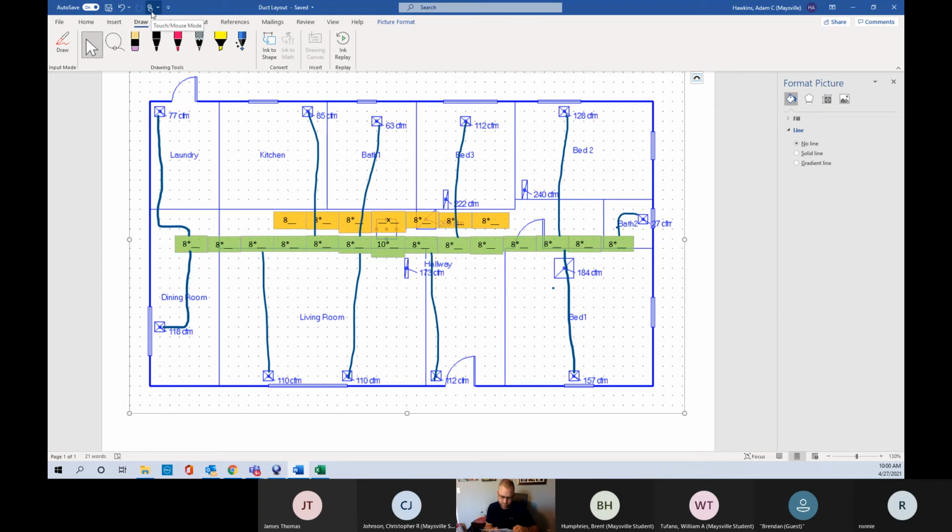I'm looking at this round. 7-inch. 7-inch, how'd you get that? I took the wire helix static pressure and lined it up with the volume CFM. Oh yeah, I'm looking at it wrong. Yes, so use the bottom blue line instead of the top one, and you line it up with the middle white column again. So if you're using flex, you can use that. The old duct calculators that I used didn't have any sort of flex correction. It was all for metal, and everybody used it for flex. Another reason why we're undersized.